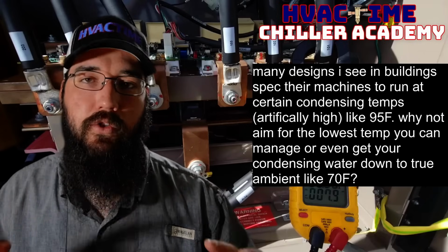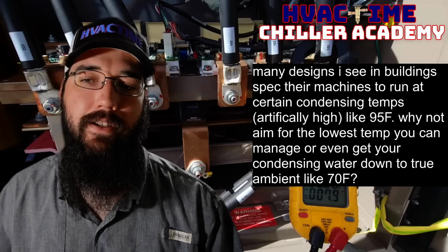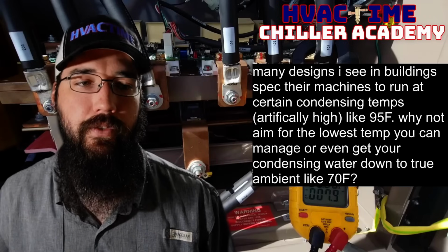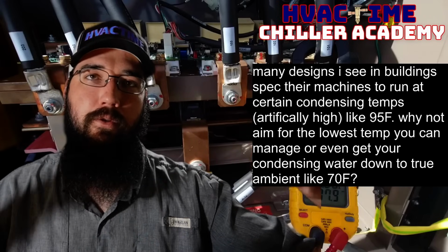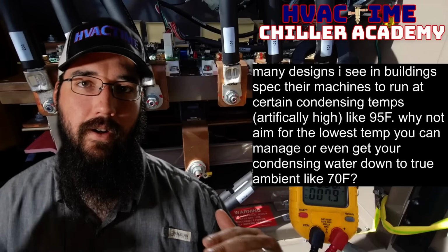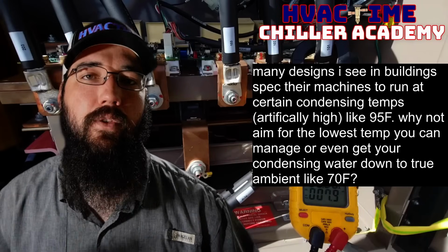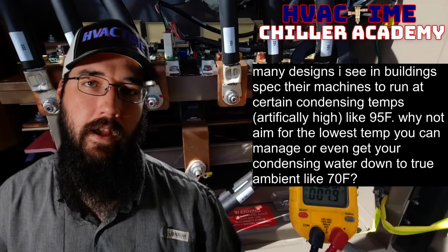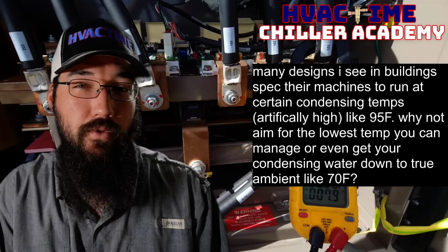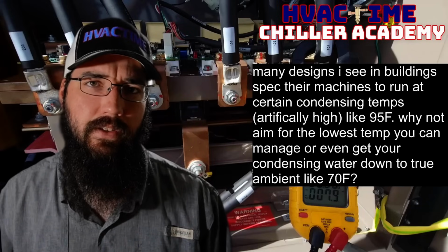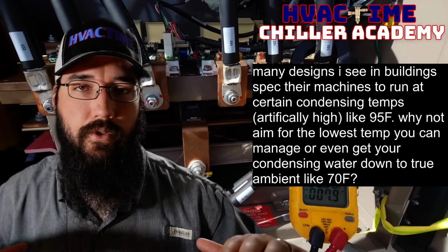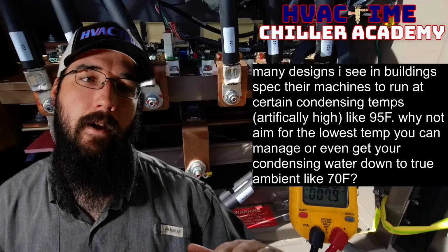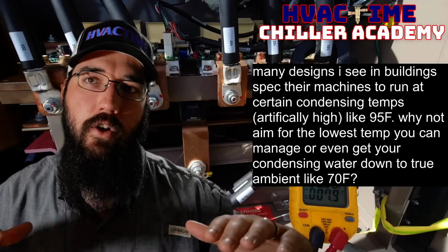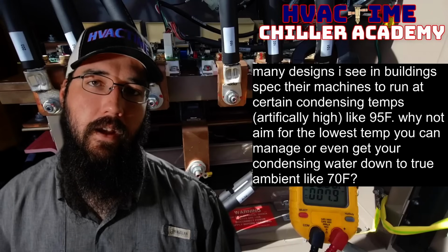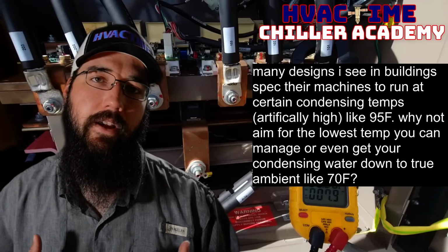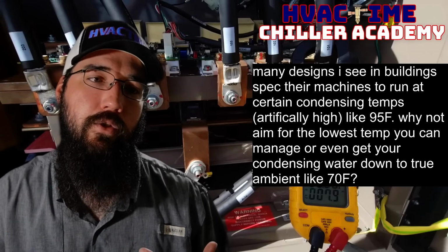Now, our ultimate goal for condenser water: the fact that we have condenser water temperatures means that we've got a water-cooled system, period. Our goal, in my opinion, should be to try to maintain as low a condenser water temperature as that chiller is allowed to handle, and do that as effectively as we can so that we can lower the amps. Because in most cases, unless we're dealing with really small equipment, a couple of degrees or several degrees of temperature change on the condenser water can mean significant load reduction on the compressor, because its amount of energy is directly correlated to how hard it's having to compress.